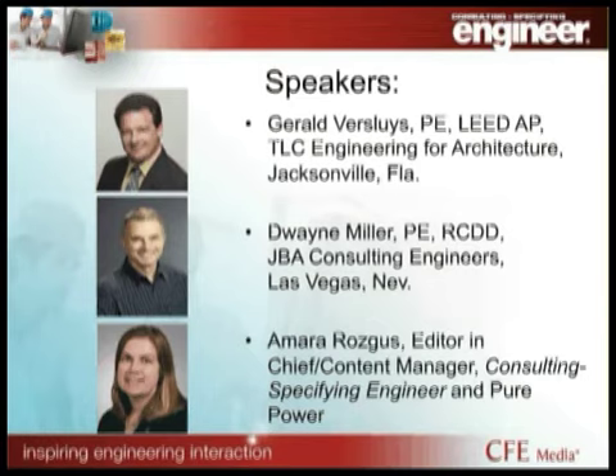You want to take that one, Gerald? No, I don't do many gymnasiums or emergency shelters. I know the language and the code keeps changing, the NEC, and basically they're trying to make all of these required to be separate systems. So I think the days of combining essential, non-essential, and these various life safety branches into one big transfer switch are gone. My recommendation is I would like to see separate transfer switches for those loads, but I'll also be the first to admit that I've never designed that type of facility.